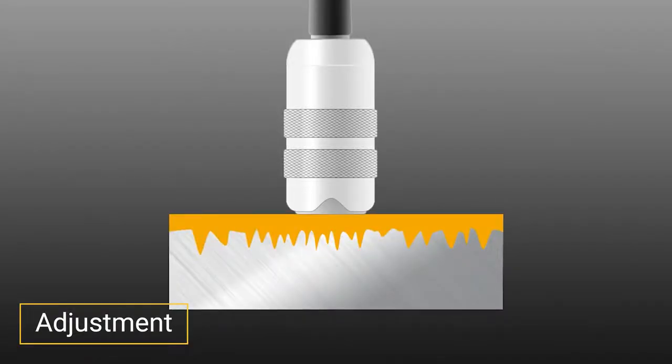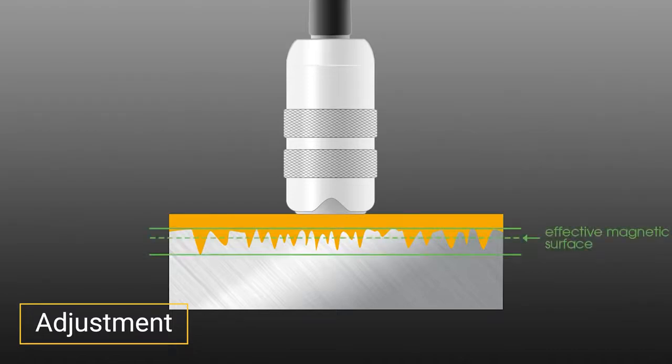Adjusting for surface profile presents a special challenge. The accepted industry practice is to measure coating thickness over the peaks of the profile, while magnetic methods result in an effective magnetic surface that is somewhere between the peaks and valleys.